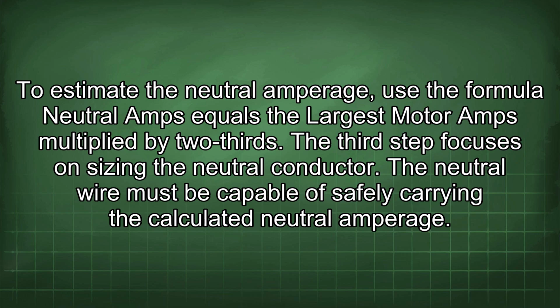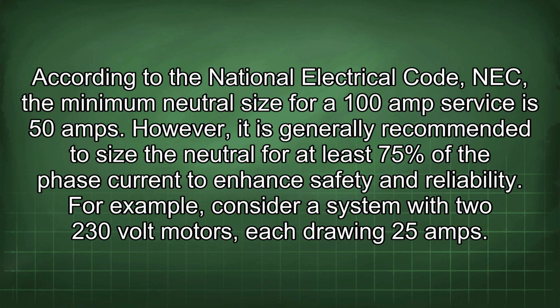The third step focuses on sizing the neutral conductor. The neutral wire must be capable of safely carrying the calculated neutral amperage. According to the National Electrical Code, NEC, the minimum neutral size for a 100 amp service is 50 amps. However, it is generally recommended to size the neutral for at least 75% of the phase current to enhance safety and reliability.